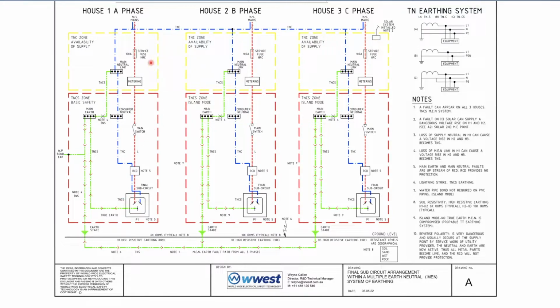So we'll go back up the top and look at the neutral. The neutral's a TNC, and so it goes down to the neutral link, down to the consumer neutral link, and then all the way through the RCD down to the final subcircuit to the neutral. And it's in this yellow zone up here, which we've termed the TNC zone, that we have availability of supply. So typically it's to keep the supply going.